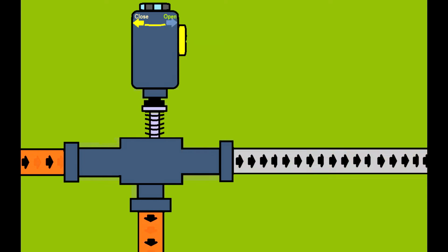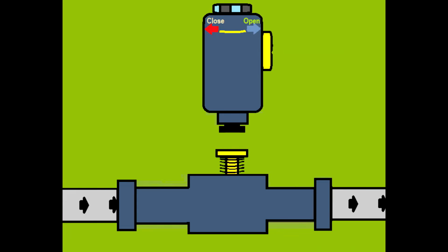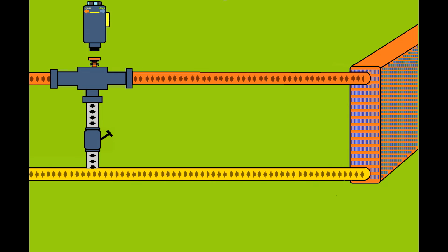Like in this case, it can be all or nothing, or it can be proportional. As you will see in this case, the glycol goes through both ways. Unfortunately, sometimes bad things happen. As you will see, the shaft of the valve is broken. The actuator tried to close the circuit, but it can't. And look what will happen now. I don't have a heat demand, but the valve is seized, and then my premises will continue to heat.